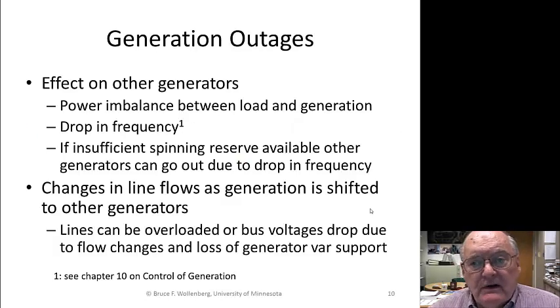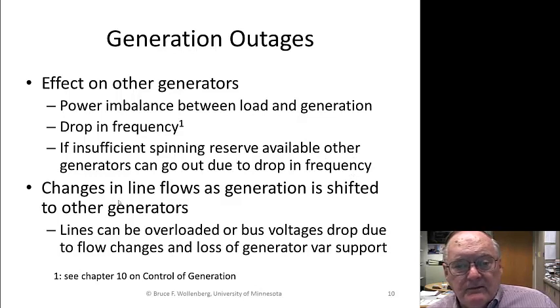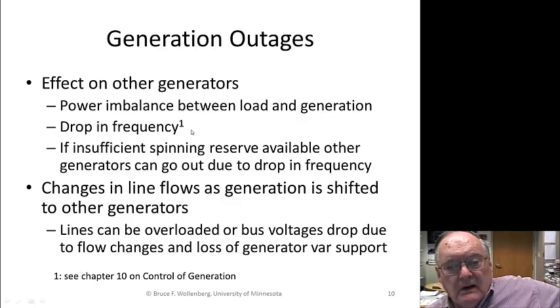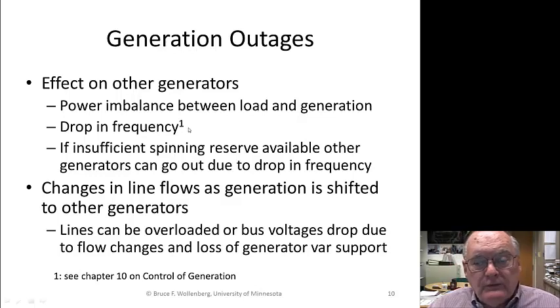Okay, now if we have generator outages, the power imbalance between the load and generation results in a drop in frequency. So when we get this drop in frequency here, then we have to make it up, and what happens is every generator goes up according to the frequency control of the system, which are governors on each generator. However, if there's not sufficient what we call spinning reserve available, meaning a generator can't go up beyond its upper limit. Well, if most of your generators are right up against their upper limit or very close to it, and then you lose one of them, the remaining generators can't go up.